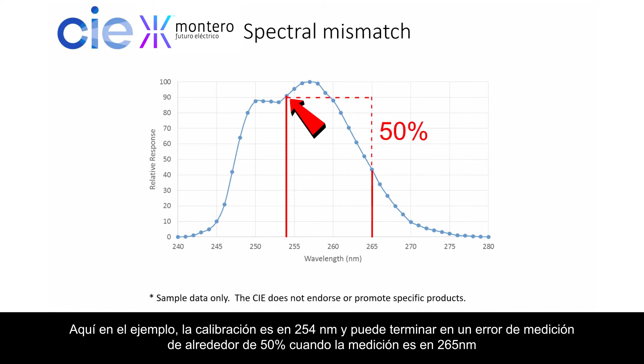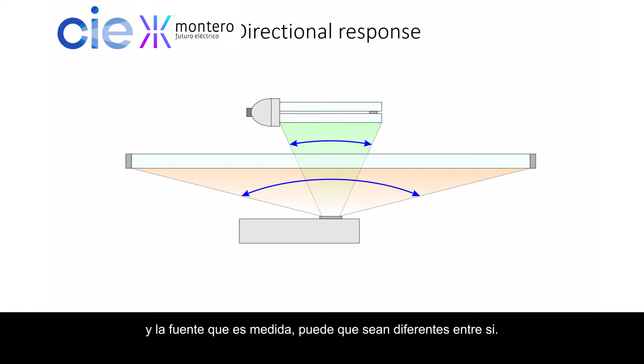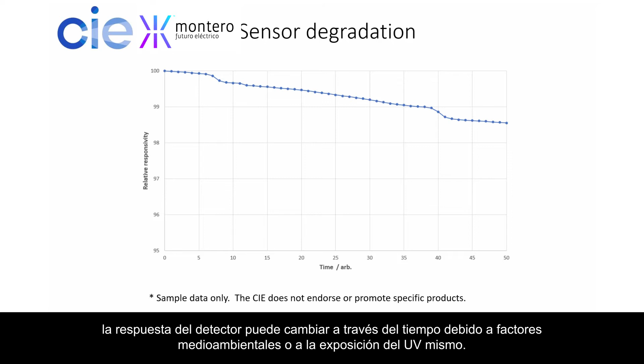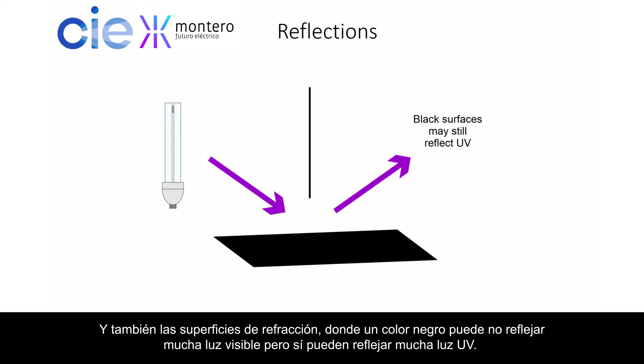It's important to read the calibration certificate and apply any corrections that are reported. Directional response. This is where the angular subtenses of the calibration source and the source being measured may be significantly different to each other. Also sensor degradation, where the responsivity of the detector may change over time due to environmental factors or due to exposure to the UV itself. And also reflectances. Surfaces that are coloured black may not reflect much visible light, but they might still reflect a lot of UV light. This is important both for the measurement and also for personal exposure.